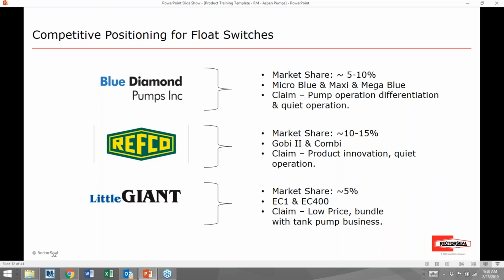A note on the Micro Blue, and we have some documentation on this, is that the Micro Blue is only suitable for 18,000 BTUs or a ton and a half. And that is at 4 inches of head. When you get up to only 5 feet of head, that pump is only capable of operating on 5,000 BTUs or less than a half a ton. Their big claim to fame is that their pump operation is different than everybody else's, and it is. It's a hybrid type of pump, and it does, in fact, have quiet operation. A couple of things we've noted over the last couple of years watching these pumps is that their pump operation can fail with dirty condensate, and these pumps do in fact get louder the longer they're in operation.